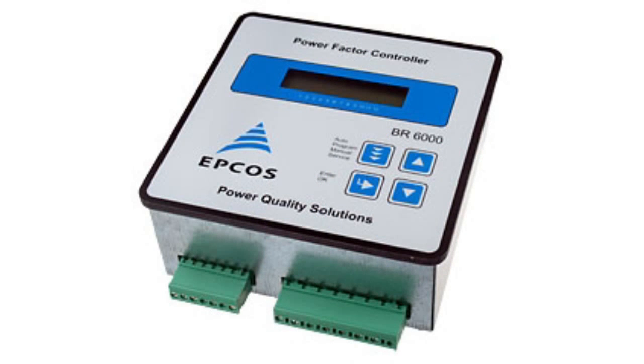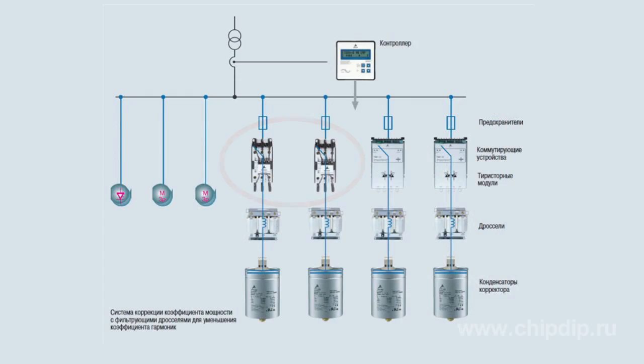Today's power factor correction controllers are based on microprocessors. A microprocessor analyzes the signal from the current transformer and transmits the signal to the capacitor bank control, connecting or disconnecting individual capacitors or entire banks. Intelligent management of correction capacitors helps provide the most efficient load of the capacitor banks, bringing to a minimum the number of switch operations, which facilitates a longer bank life.